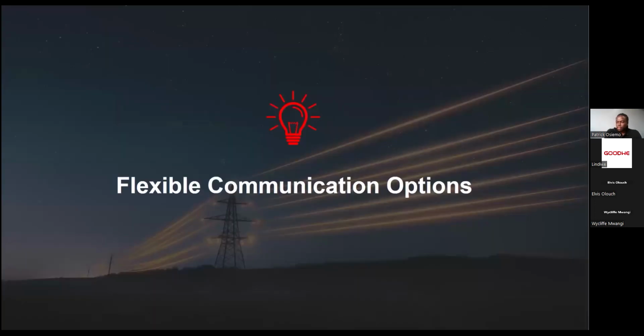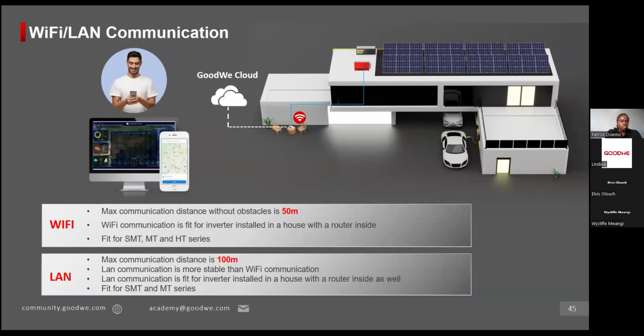We noted that there are different ways that you can communicate with various smart devices. So GoodWe inverters are also smart in the same manner, and they offer various ways of communicating, configuring, or monitoring them. For example, we have Wi-Fi and LAN. If you're limited to 50 meters of communication, then inverters can communicate through Wi-Fi. If you want to extend this distance to 100 meters, then you can use the LAN protocol.